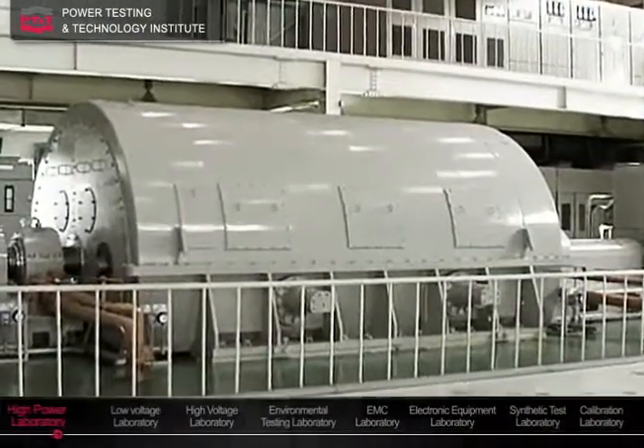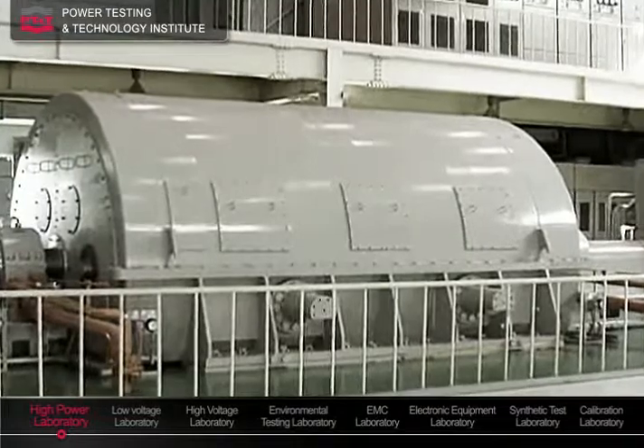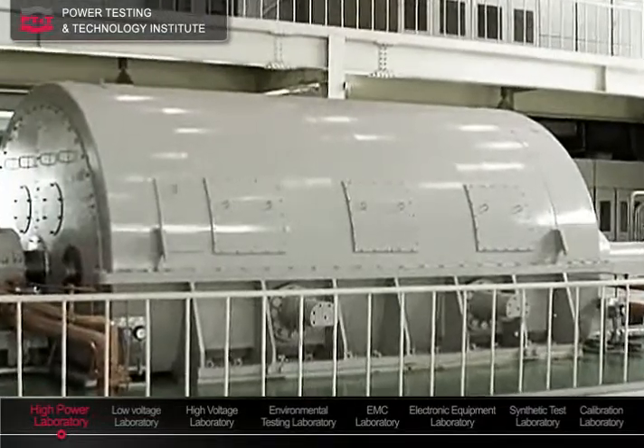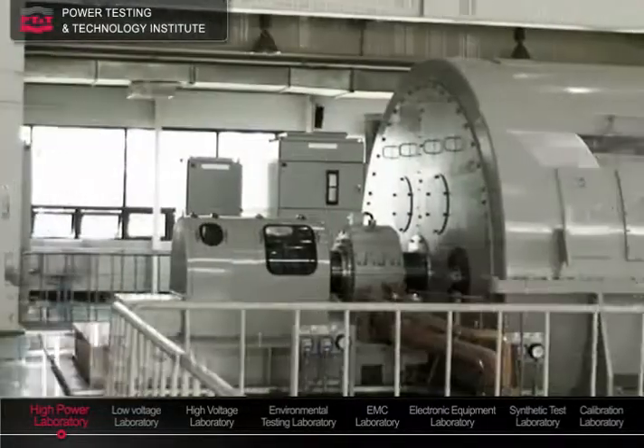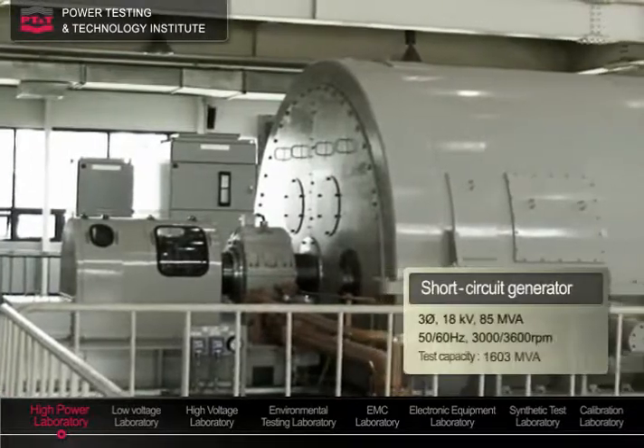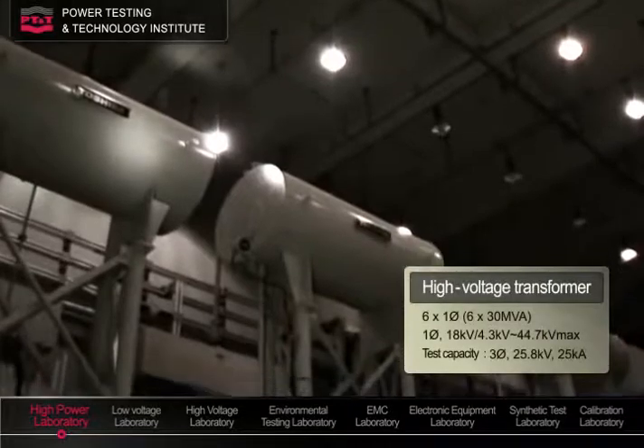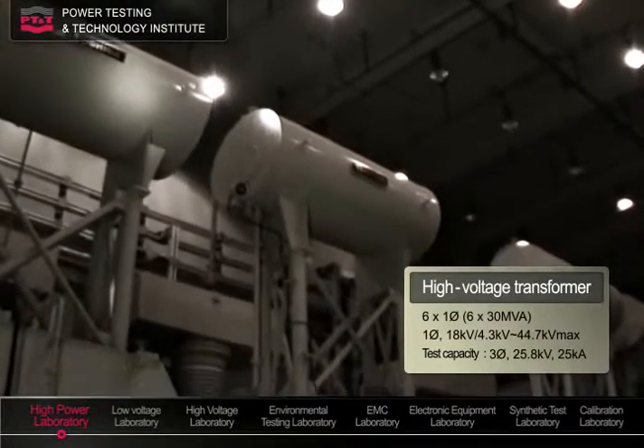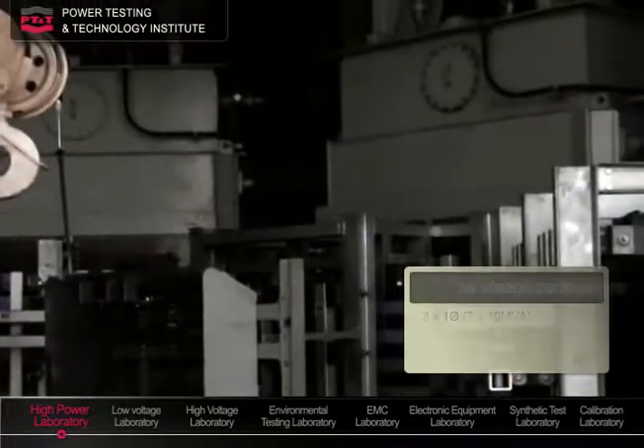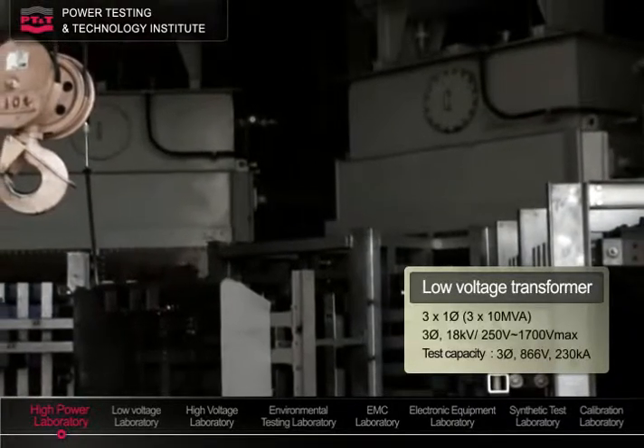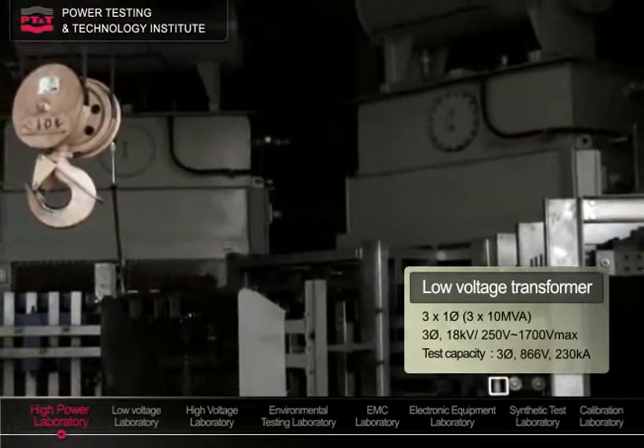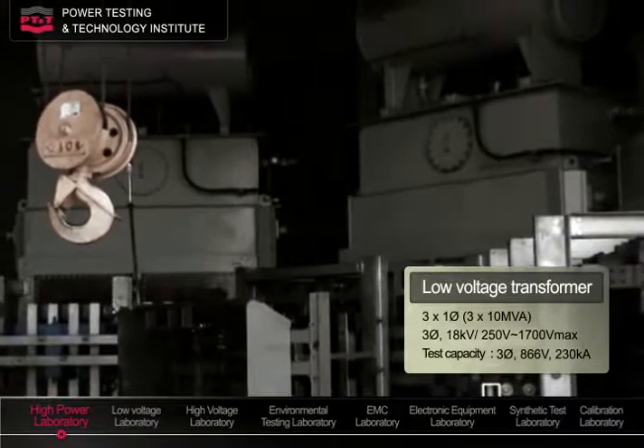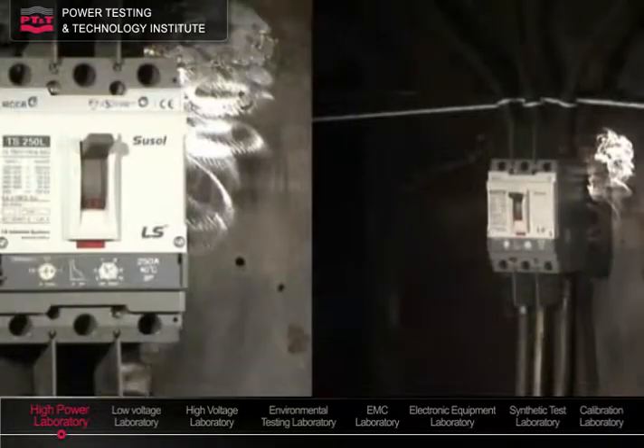High Power Laboratory simulates the fault conditions in power system. For this, short-circuit generator, high voltage, and low voltage testing transformers are used for testing power sources to verify the electrical and mechanical performance of circuit breakers, disconnecting switches, switch gears, fuses, and many other electrical equipment.